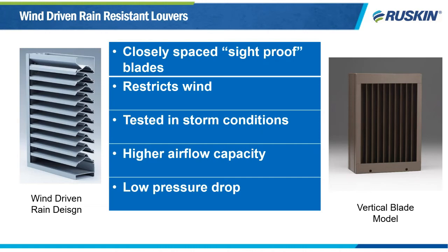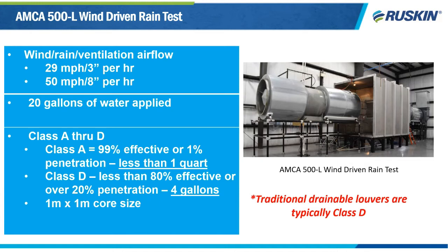Here we'll take a look at the AMCA 500L wind-driven rain test. In this test, the louver is subjected to wind, rain, and ventilation airflow. In the picture on the right, you'll see that unlike the still air test we saw a few slides back, this test utilizes a wind fan and water nozzles directly in front of the louver. Water is driven into the louver core by the wind fan.